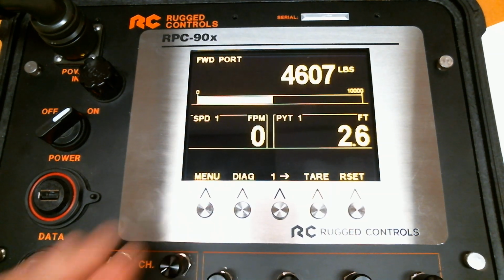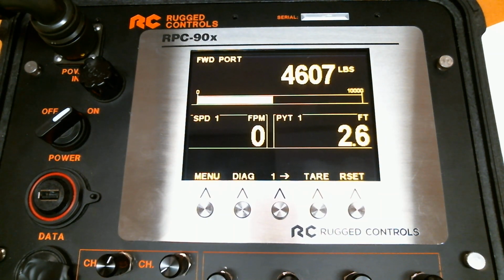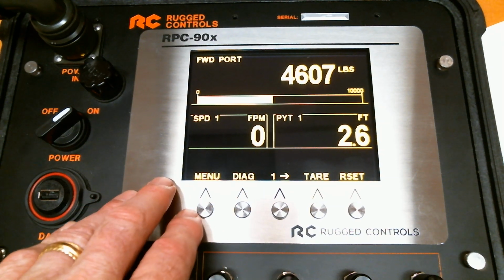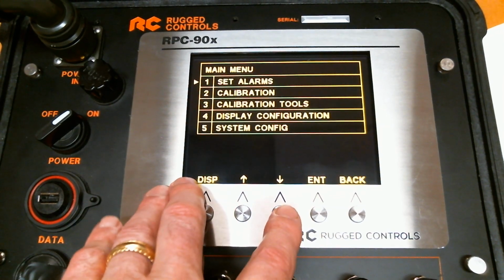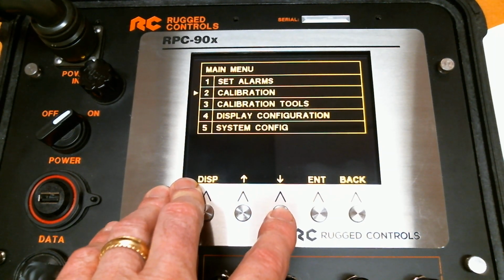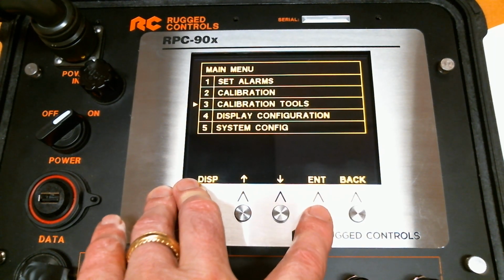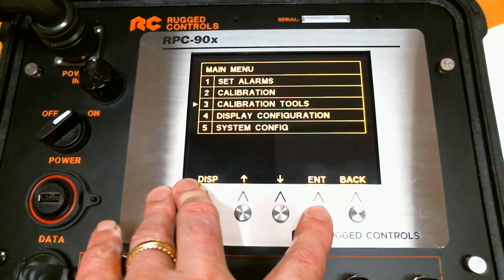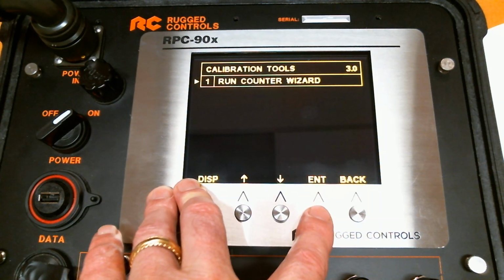A better approach is to do a live calibration where you will need to put 2 marks on the line a known distance apart. Probably take a tape measure, roll out 10 feet, 20 feet, whatever is feasible, with 2 marks at each end of the measurement. And we will use that to do a live cal for payout and speed. We will use our calibration tools, row 3. We will run the counter wizard.